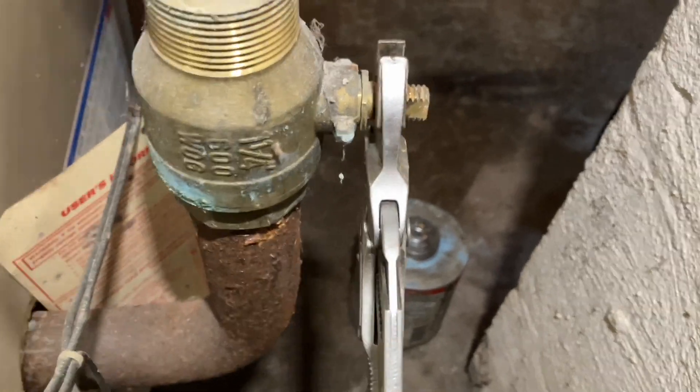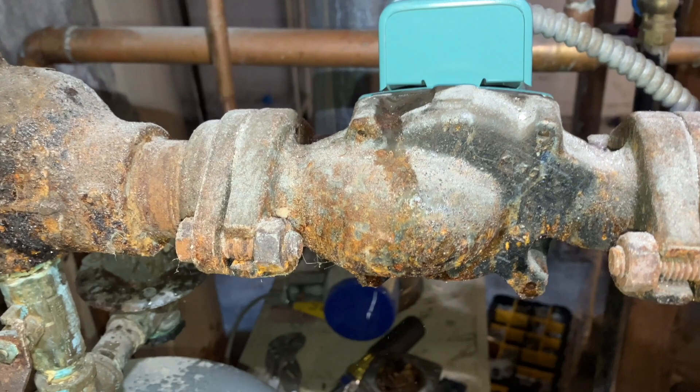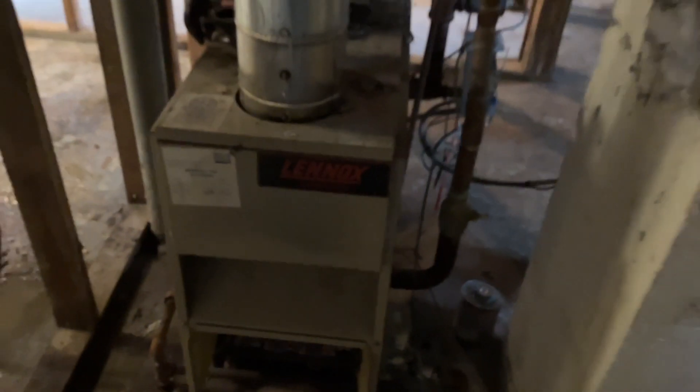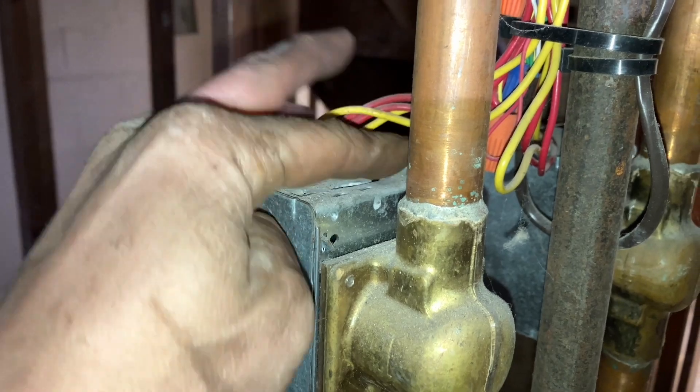If we're purging over here, we want to shut down over here. This ball valve is officially stuck — it's fine, it's just going to make purging the system a lot more difficult. Currently looking for that other thermostat because there's two zones — we'll just jump it out. I messed up, I should have swapped this part out earlier. That's all right, I'll do it right now. Sounds like it's got air but it sounds a lot better. Looks like that zone is actually working, so we're good there. Now I'm just gonna wait and see if the place heats up.